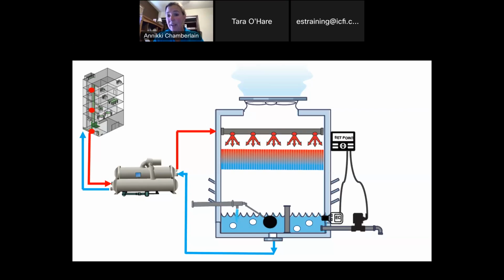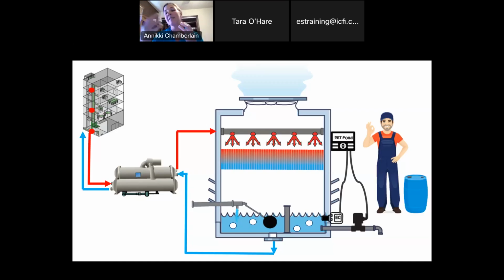So who's responsible for understanding what the set point is and maintaining this equipment is this person, our service provider, usually a water treatment technician that we've hired to come in and operate this cooling tower as optimally as possible. The balance here is to use the water as much as we can to be efficient, but not so much that the mineral concentration causes scale inside the chiller or on the tower. Oftentimes, what we're purchasing with this person is a water treatment program, which typically includes some kind of chemical addition to keep those minerals in solution as long as we can to prevent them from hardening, creating that rock barrier on the surfaces where we want to exchange heat. So that's basically the quick overview of how towers work.